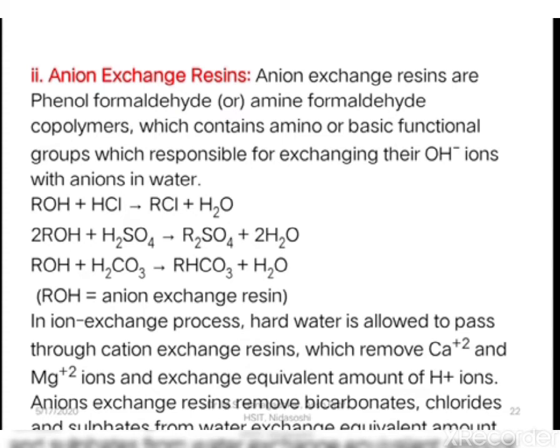Now let us discuss how the process of exchange takes place in the anion exchange resin compartment, that is the second compartment. Anion exchange resins are what? Usually made up of phenol formaldehyde or amine formaldehyde copolymers containing either amino or basic functional groups, which are responsible for the exchange of the hydroxyl ions with anions. Hydroxyl ions from the ion exchange resin are exchanged by accepting anions like chloride, nitrate, sulfate from the water.